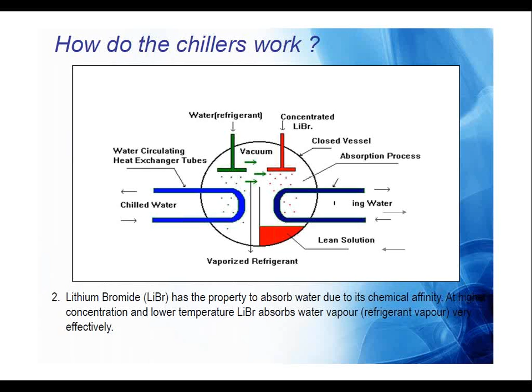So this required temperature cooling water will enter into this absorber, take away the heat of exothermic reaction, and typically comes with a delta T of 3 to 4 degrees. So for example, 32 degree cooling water is entering the absorber. It will take away the heat and it will come out at around 34-35 degree. Then the same water will enter into the condenser for removing the condensation heat. I'll come to that later.